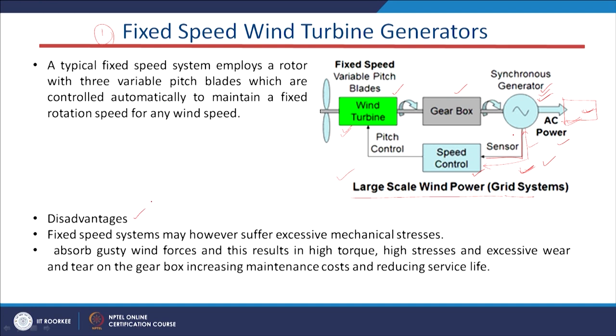What are the disadvantages of this type of wind generating system? The first one is the fixed speed systems may suffer excessive mechanical stresses. The second one is it absorbs the gusty wind forces, and this results in high torque, high stresses, and excessive wear and tear. The maintenance cost increases and the wear and tear mechanism is basically on the gear box.